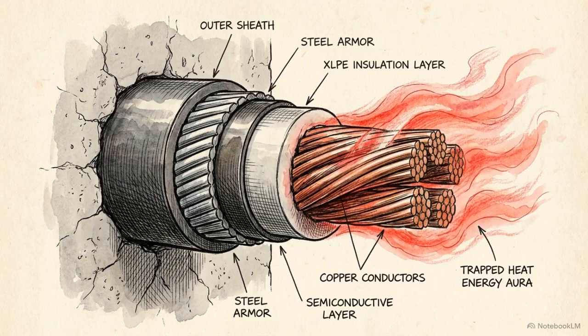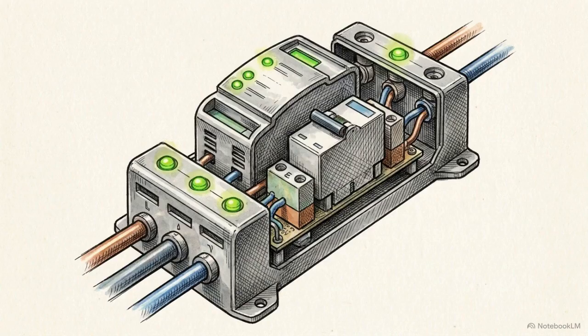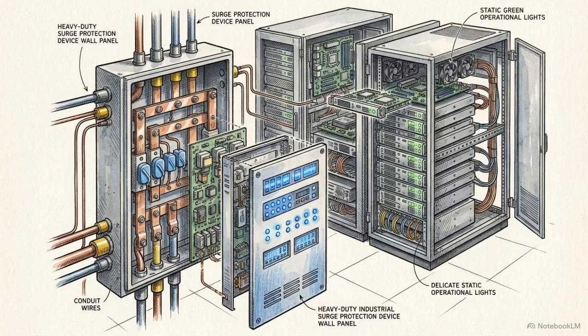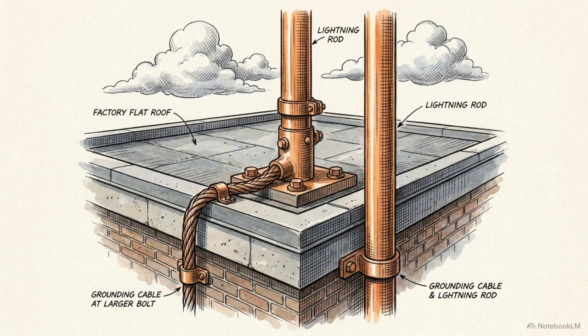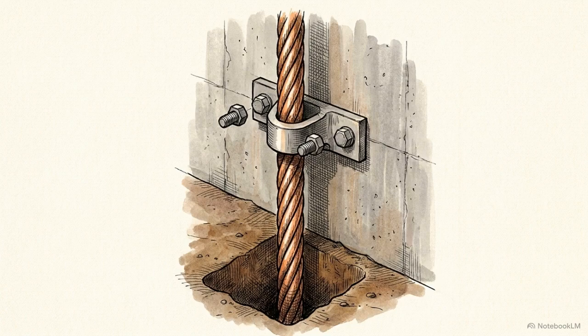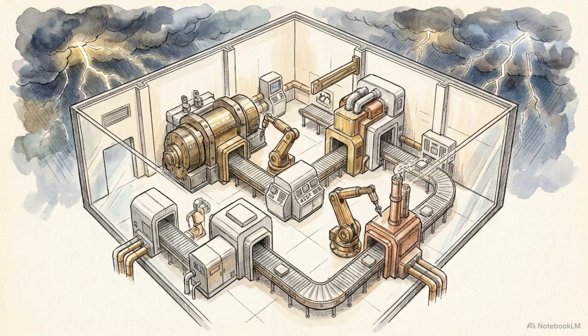But sometimes, a tiny ripple of that shockwave tries to sneak its way inside through the power cables. To stop that, engineers install surge protection devices, or SPDs. Think of them as heavy-duty shock absorbers that catch and neutralize those leftover electrical spikes before they can reach the sensitive equipment. The goal of external electrical protection is not to fight the storm head-on. Instead, the design simply provides a highly attractive path of least resistance, guiding the danger safely around the critical machinery.